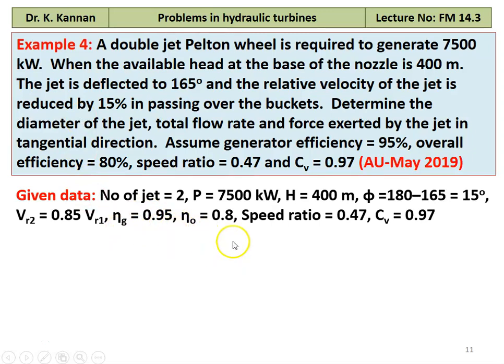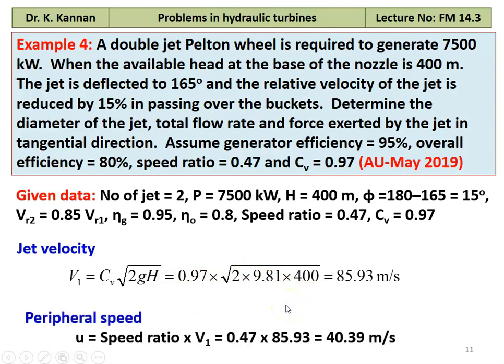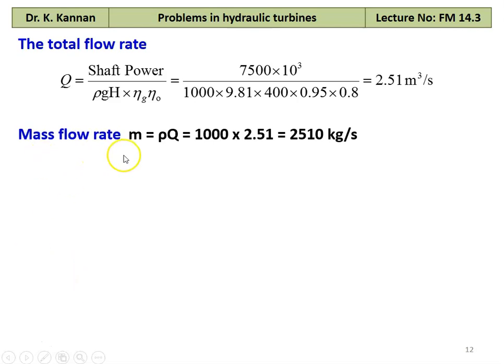Jet velocity V1 = 0.97 × √(2 × 9.81 × 400) = 85.93 m/s. Peripheral speed U = 0.47 × 85.93 = 40.39 m/s. Total discharge Q = shaft power / (ρGH × generator efficiency × overall efficiency) = 7500 × 10³ / (1000 × 9.81 × 400 × 0.95 × 0.8) = 2.51 m³/s. Mass flow rate M = ρQ = 1000 × 2.51 = 2510 kg/s.